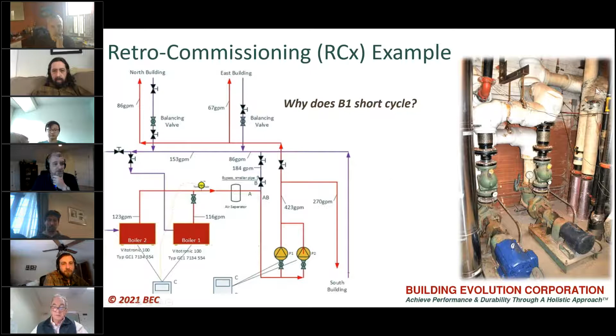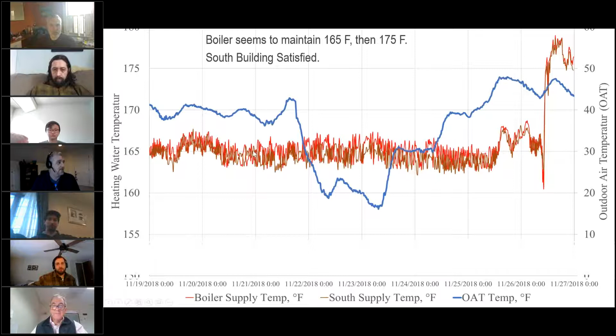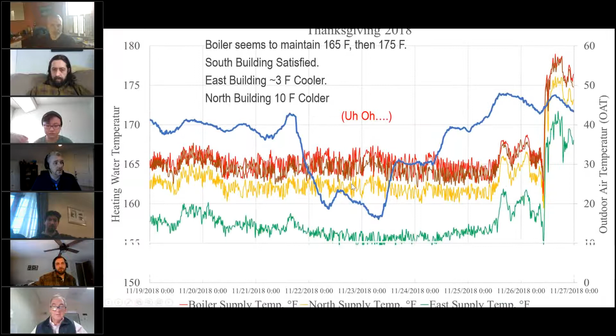Well, if we start to look into it, the south building gets the water off the boiler system first, and it's okay. It's satisfied. The boiler that gives out hot water, it gets hot water. When we get to the east building, it gets a few degrees colder. The north building is 10 degrees colder. That's the third takeoff off the building loop.